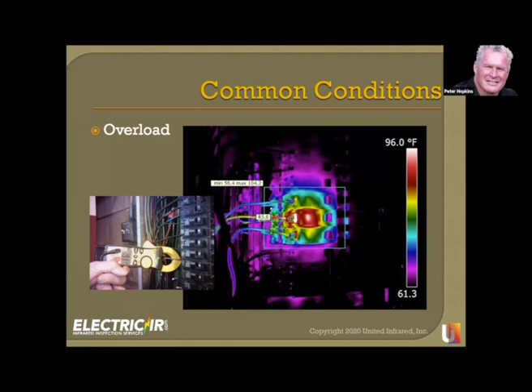This is a 20-amp breaker. What is the maximum load that can go on a 20-amp breaker? By now you've answered this question. The maximum load is governed by the 80% rule, established in the electrical code.